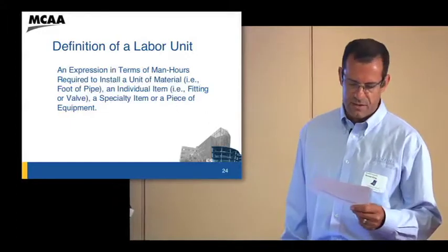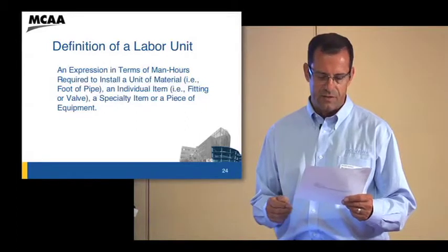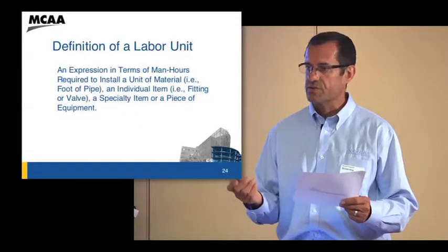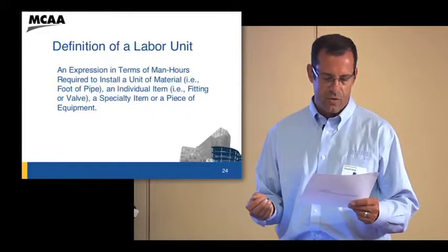Let's talk about the definition of a labor unit for a second. This is how we define the labor unit. It's an expression in terms of man hours required to install a unit of pipe, or a unit of material such as a foot of pipe, an individual item such as a fitting or a valve, a specialty item, or a piece of equipment. One thing to note is that with the WebLEM's approach, everything in there has to have labor on it. Everything needs labor. That's something you really need to think about when you're doing an estimate: make sure everything gets labor.